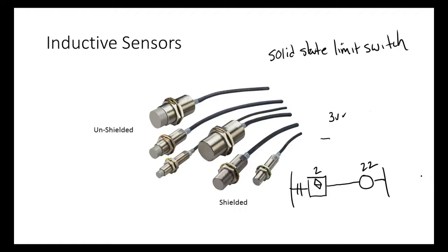You understand that? So the problem with these solid state limit switches is they drop a voltage. If this was a limit switch and the limit switch was good, how much voltage would it drop? Zero, right? You understand that? Unless something's wrong with the switch.